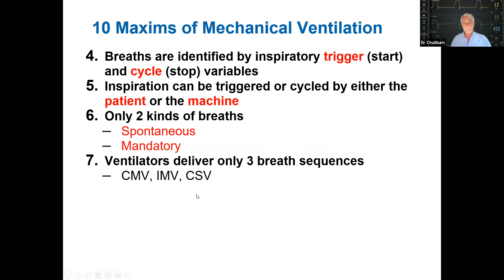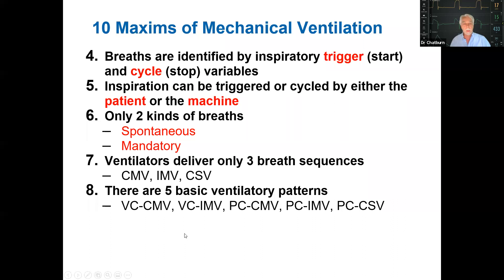All modes of ventilation can be categorized in terms of three breath sequences: continuous mandatory ventilation (CMV), continuous spontaneous ventilation (CSV), or intermittent mandatory ventilation (IMV). Pairing control variables — pressure or volume, derived from the equation of motion — with these breath sequences gives us five generic modes: volume-controlled CMV and IMV, and pressure-controlled CMV, IMV, and CSV. This makes classifying hundreds of mode names much more practical.